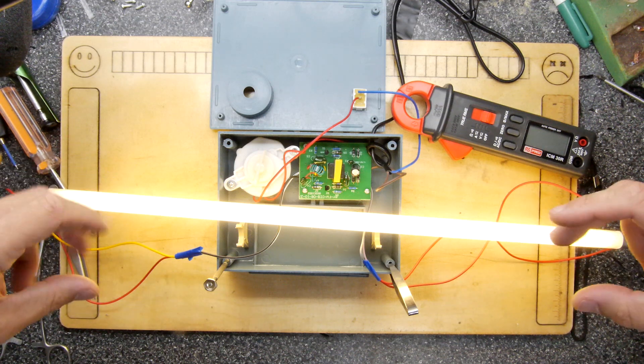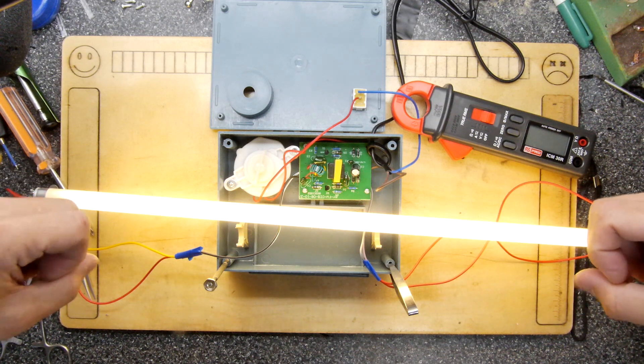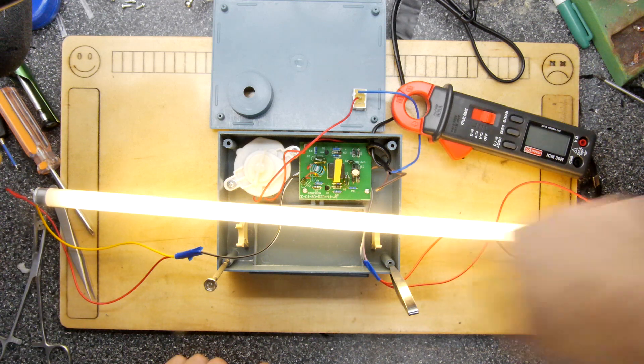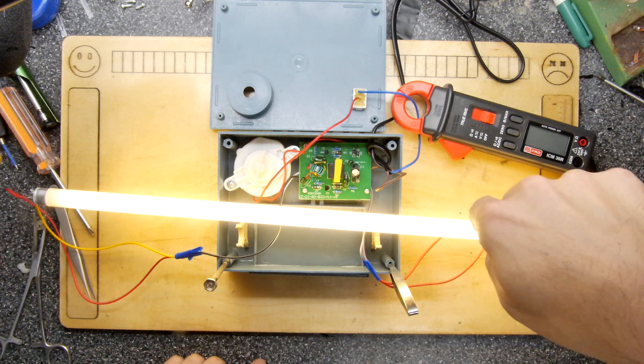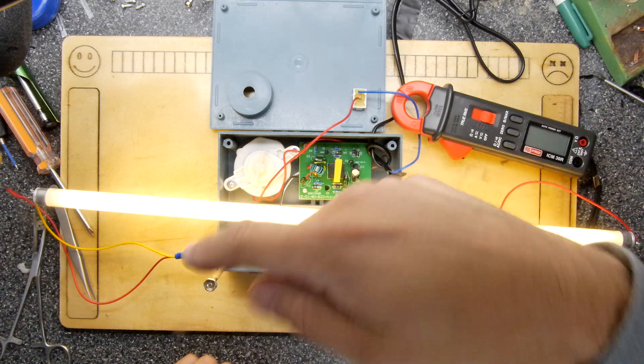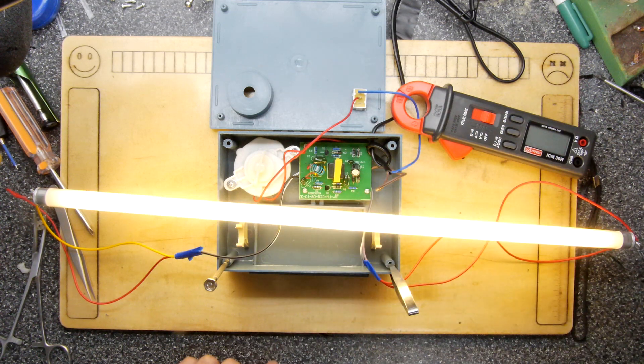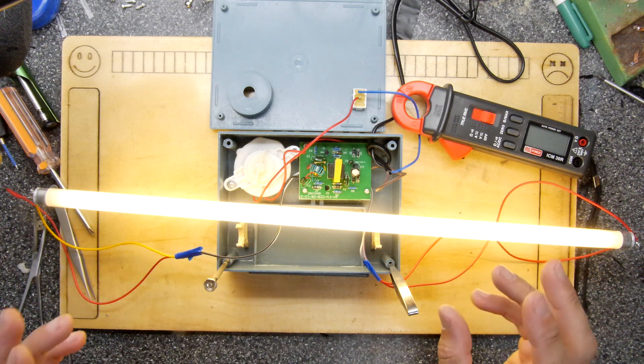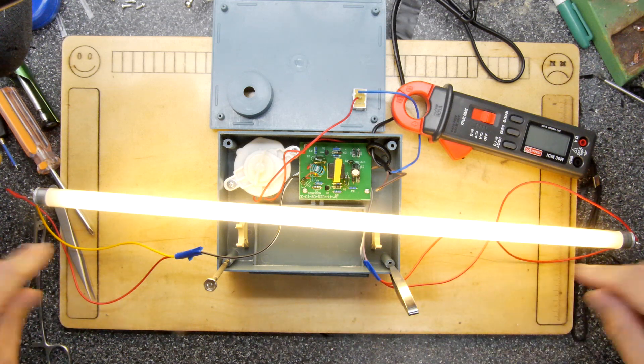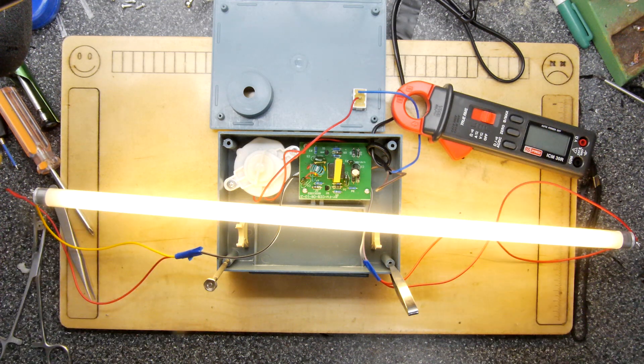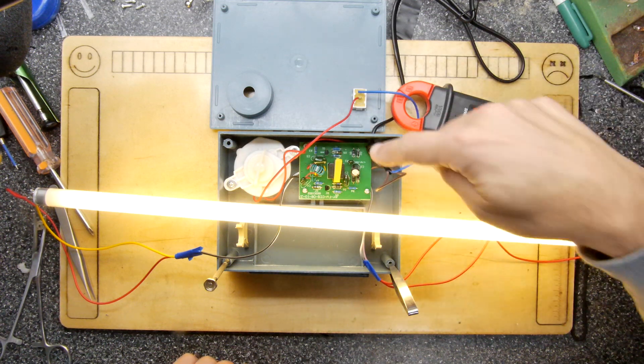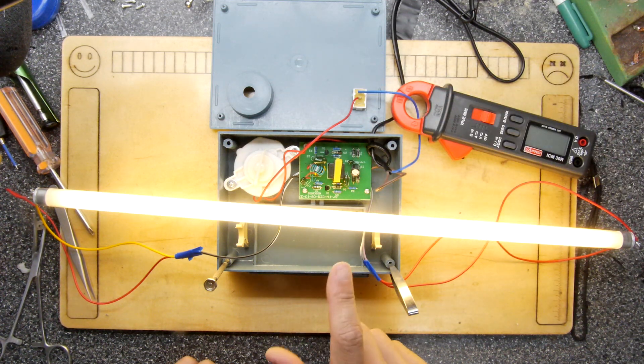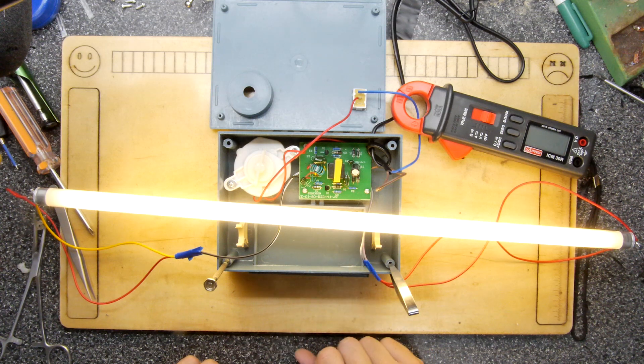And then going, normally there's a dink, dink, dink. Remember the old fluorescent tubes in your kitchen doing that dink, dink, dink? That's putting, you know, normally a capacitor discharge across to get some sort of high voltage path to go through. And then once that's ignited, normally those sort of mechanical ballasts, they would disconnect part of that circuit and then it would just keep running. And this is literally just a digital version and no different at all to the digital things that you'd have.